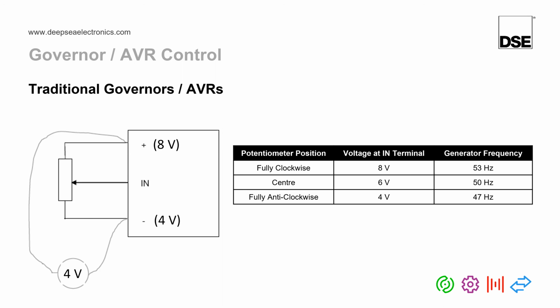One way to know if your governor or AVR is actually going to work with a Deep Sea module is if you were to take a DC multimeter and measure the voltage between what would be the minus and the plus terminal. As long as that voltage, as shown here as 4, is less than 10 volts, it will definitely work with the Deep Sea unit.